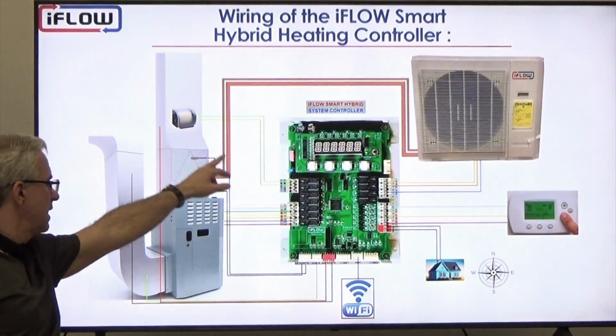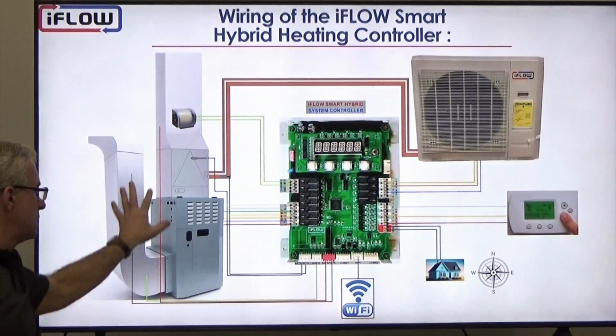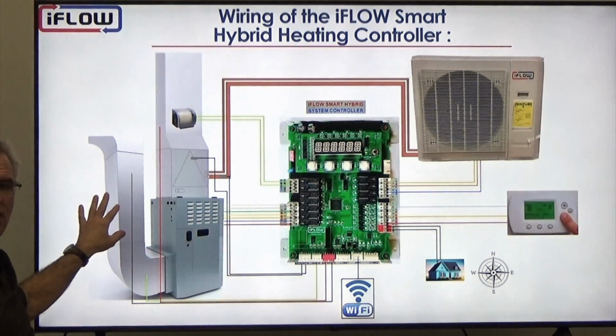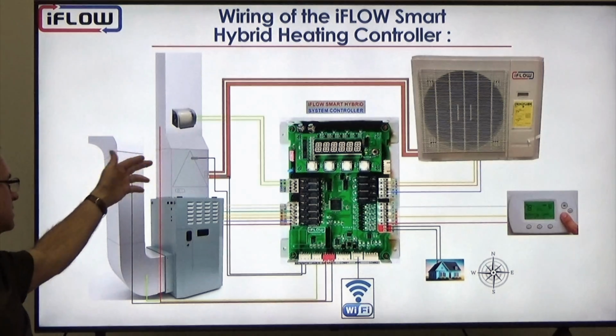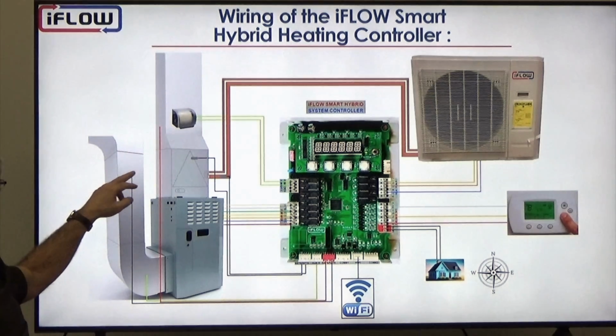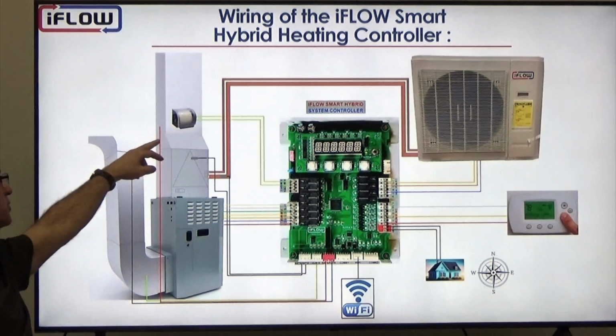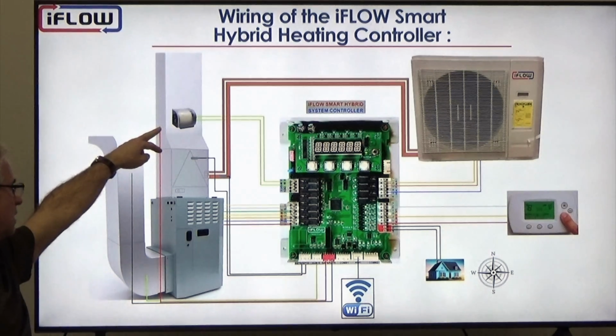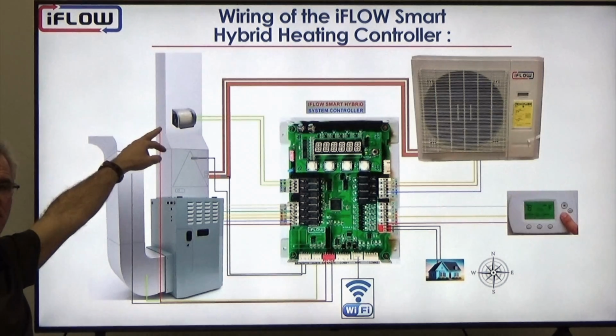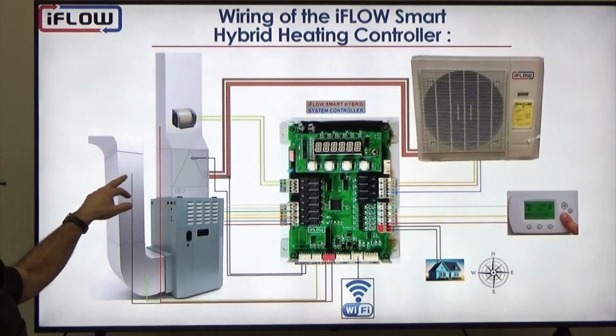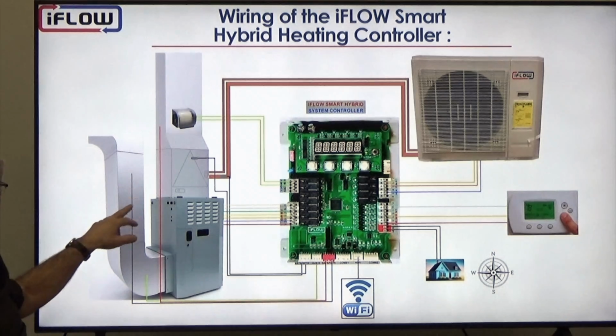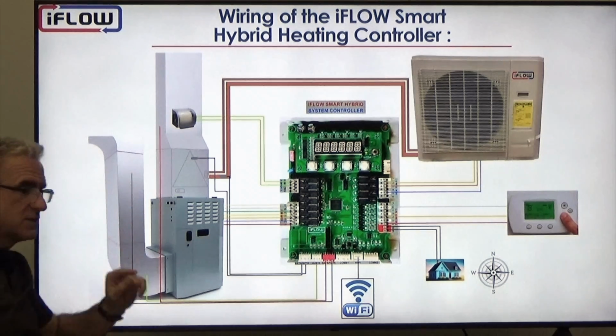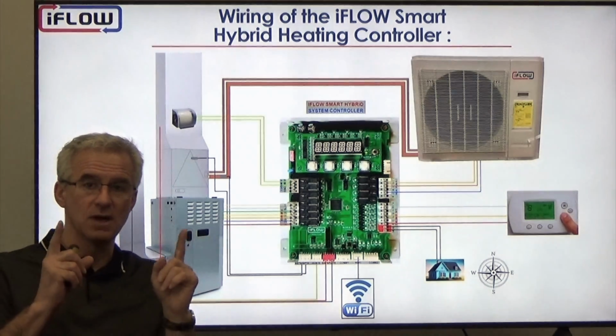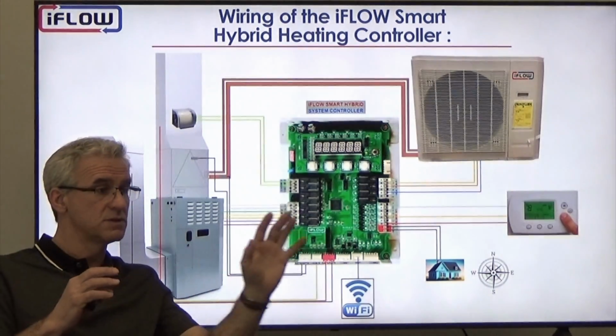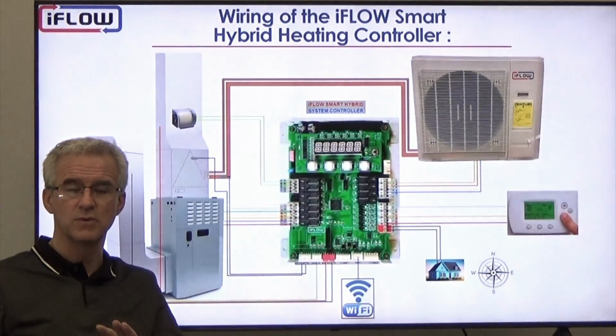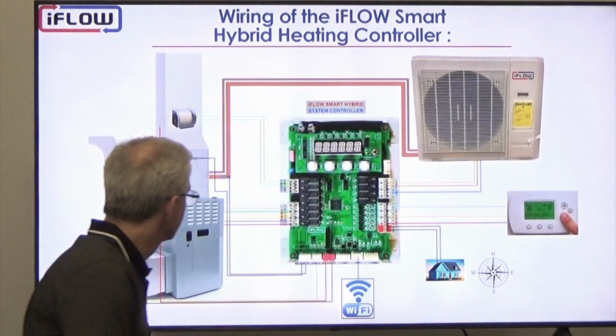When we look at the connections of the sensors that we include in the kit and how they connect to the furnace or the ducting, for example, we have our supply and our return air temperature sensors. So we have our supply sensor in the ductwork above the evaporator, and then we have our return air temperature sensor somewhere in the return ducting. That's going to tell us what our delta T is across the heating system, whether it's the furnace that's running or whether it's the heat pump that's running. We'll be able to tell what the delta T is.